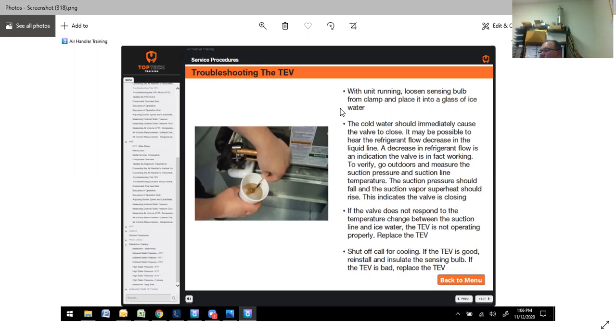To verify that, go outside and look at your suction pressure and temperature again. The suction pressure should fall and the suction vapor superheat should rise. This indicates that the valve is closing. You can also do that again if you want to open it up. You can put it in a glass of warm water, or you can hold it in your hand, or any combination. But if you heat it up, it's going to open it. If you put it in ice water, it's going to close it. But as you do this, you should see wild fluctuations. If you see very minor fluctuations, then you probably have a defective TEV.